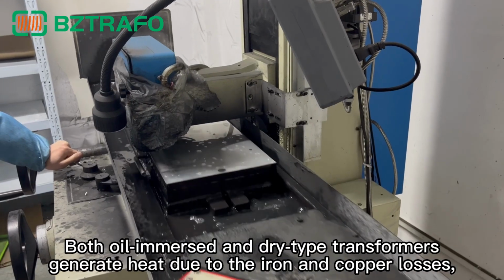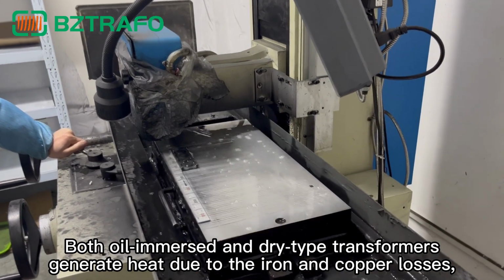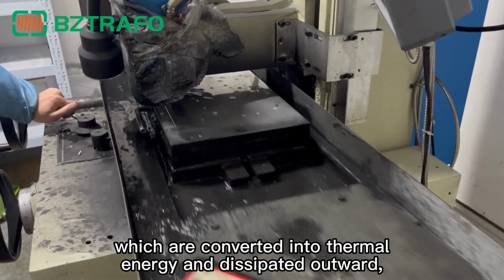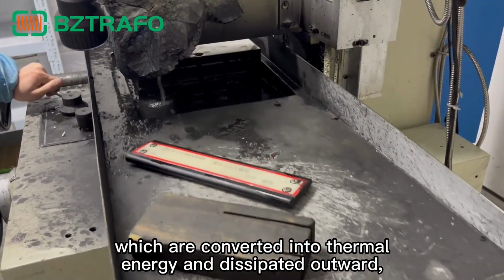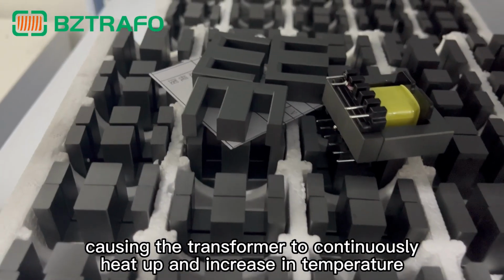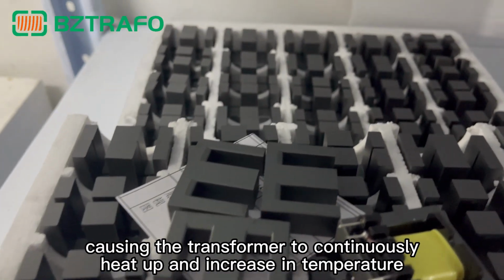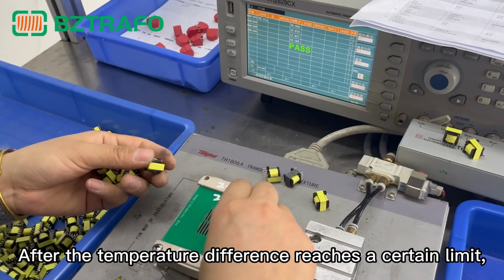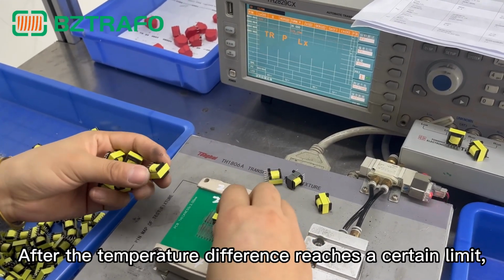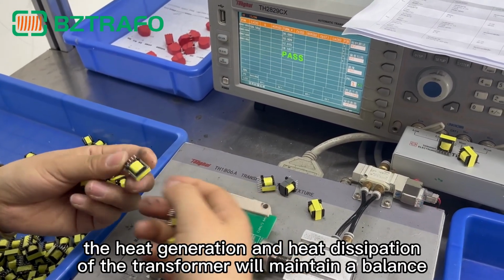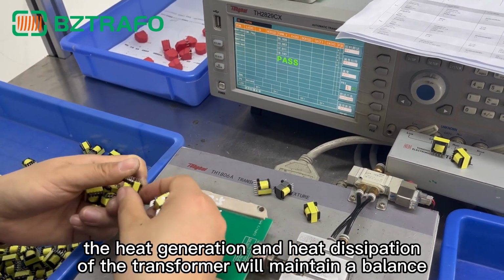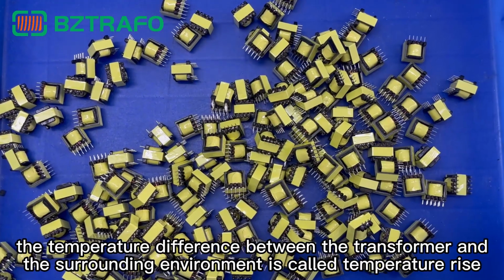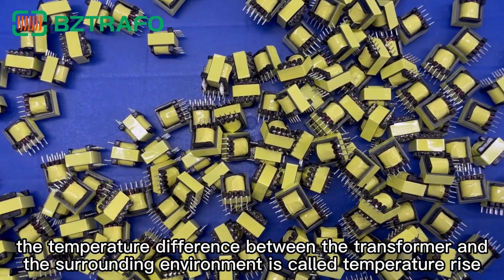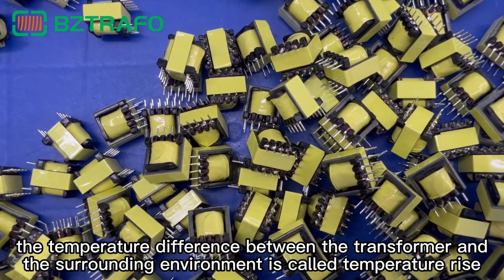Both oil-immersed and dry-type transformers generate heat due to the iron and copper losses, which are converted into thermal energy and dissipated outward, causing the transformer to continuously heat up and increase in temperature. After the temperature difference reaches a certain limit, the heat generation and heat dissipation of the transformer will maintain a balance. At this time, the temperature difference between the transformer and the surrounding environment is called temperature rise.